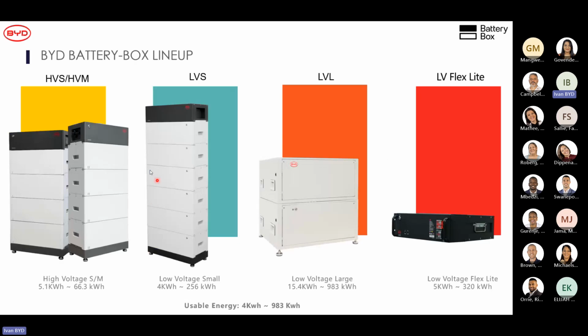So here's some reasons why to use BYD. Short lineup of their portfolio. On our left, we've got the high voltage batteries, which have a capacity of the modules of the batteries from 5.1 kilowatt hours all the way up to 66 kilowatt hours on the HVS and HVM. On the LVS, so low voltage battery, you can have between 4 kilowatts all the way up to 256 kilowatt hours. LVL starts at 15.4, and you can go all the way up to 983 kilowatt hours, which is nearly a megawatt hour. And on your Flex Lite, they're 5 kilowatt hours per module, and you can go all the way up to 320 kilowatt hours.